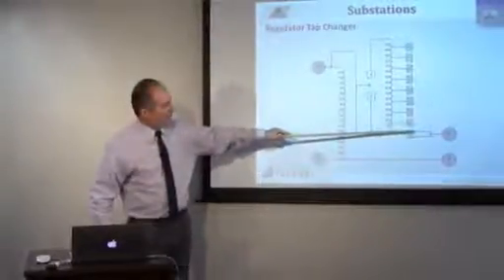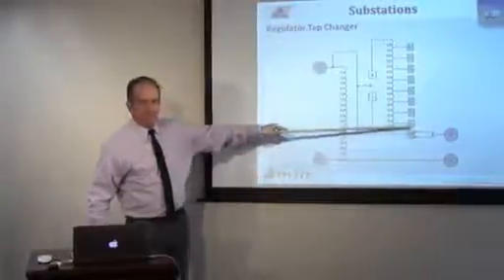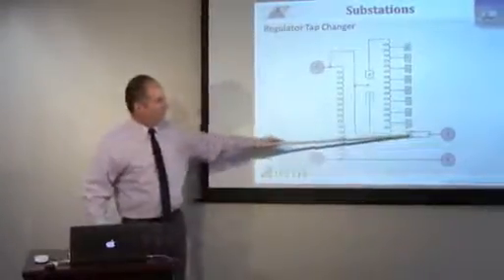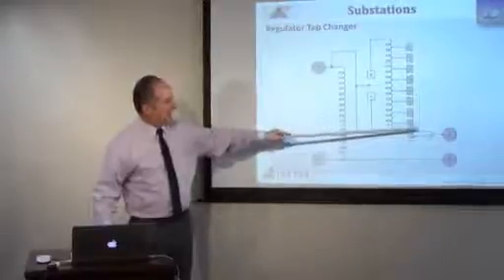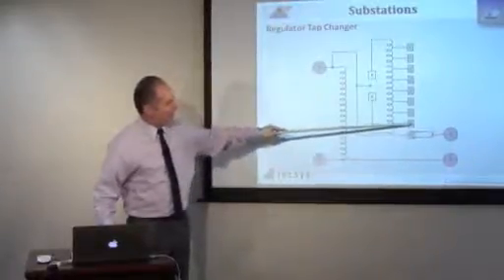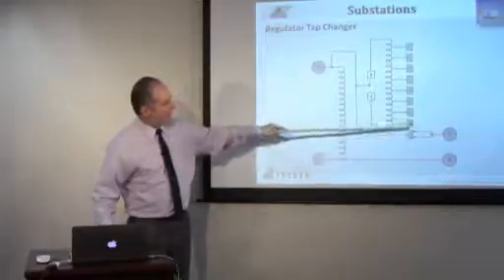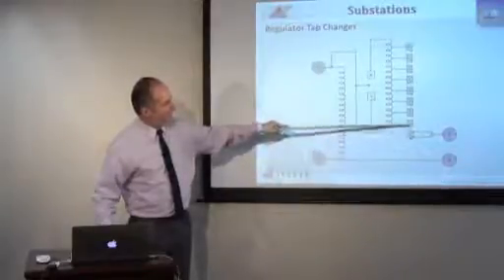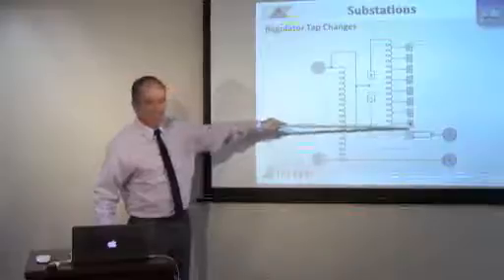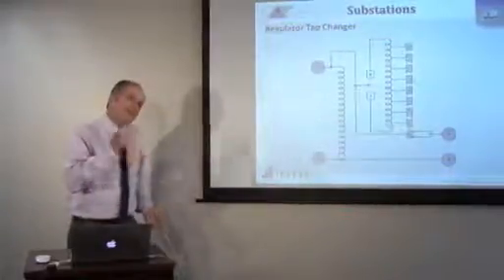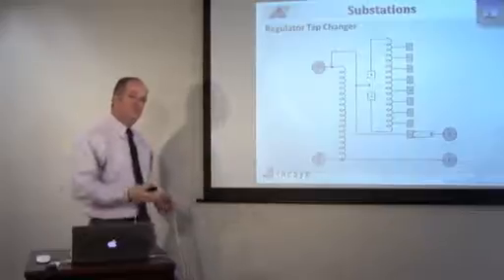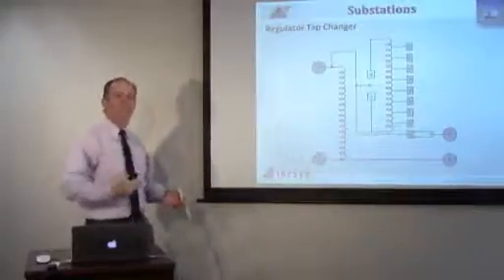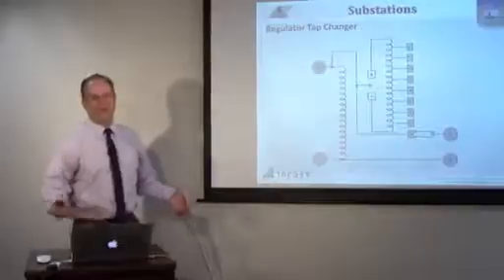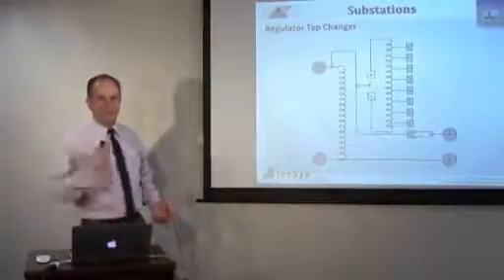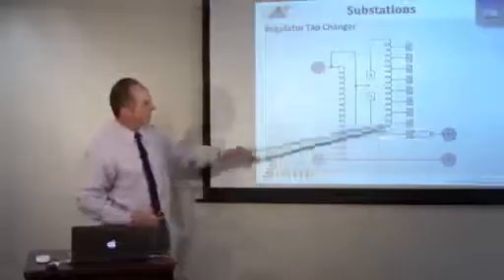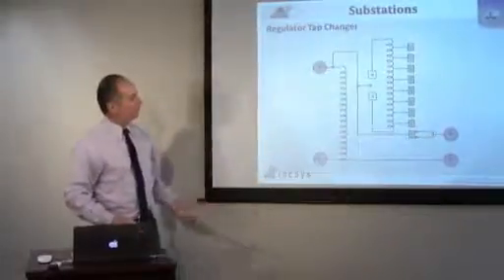And with a regulator, what's very important to know is that the load bushing actually has 2 connections. It actually has to make before break so that you don't get arcing. So when you want to raise the tap, this connector goes to here. Now the load is connected to 2 taps, raising the voltage, and then if you have to go higher, this one goes up to there. But there's always a connection. As long as there's always a connection, you minimize the arcing. If you don't minimize the arcing, you get gas in oil. If you get gas in oil, the dielectric strength goes down and you have a regulator failure. So you've got to clean the oil, get the gas out, and you have this type of operation.